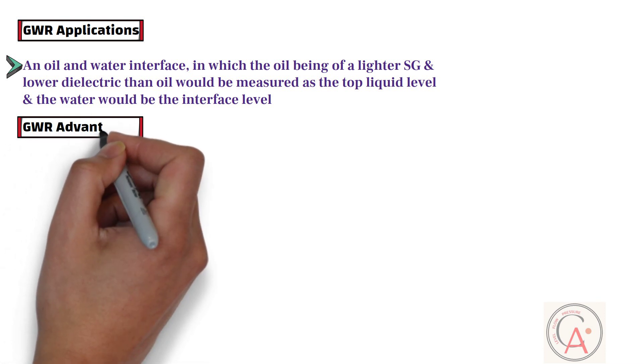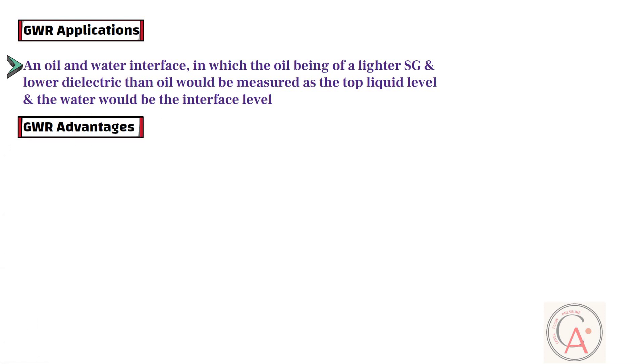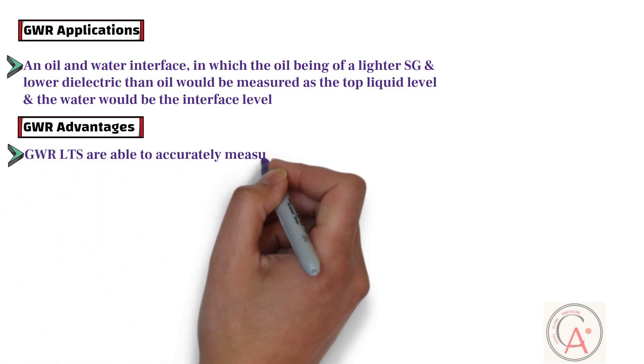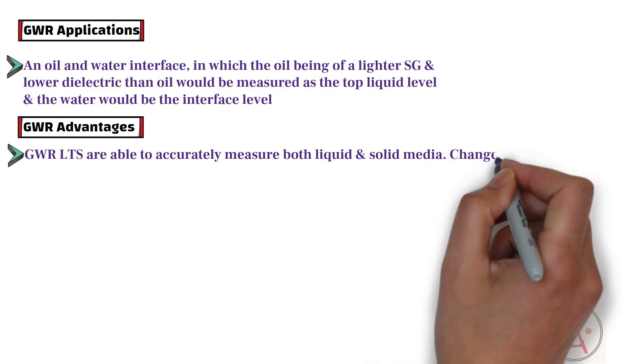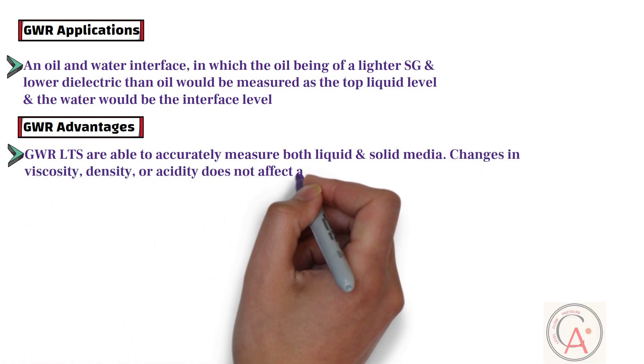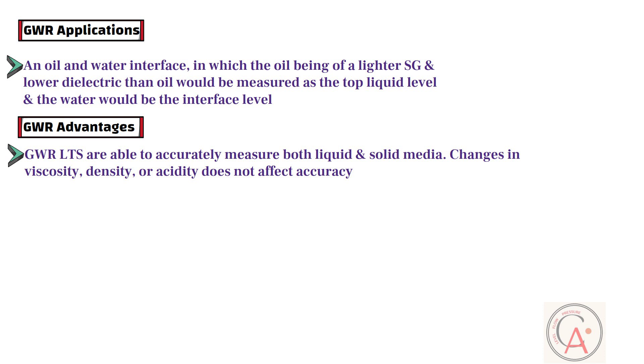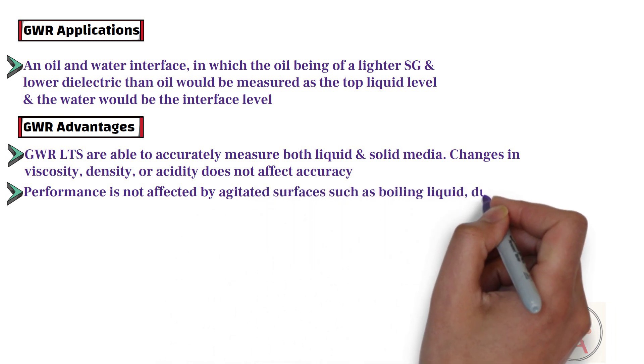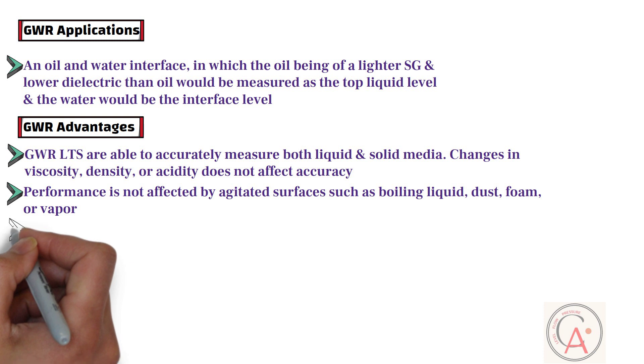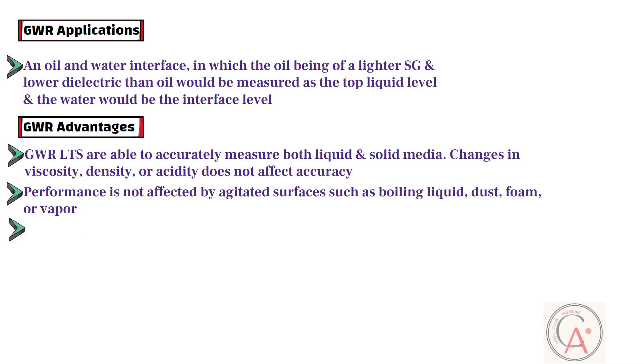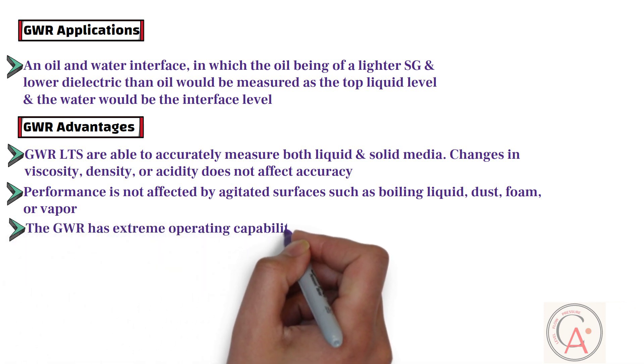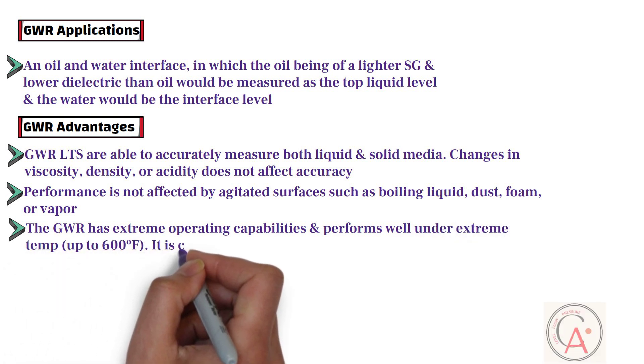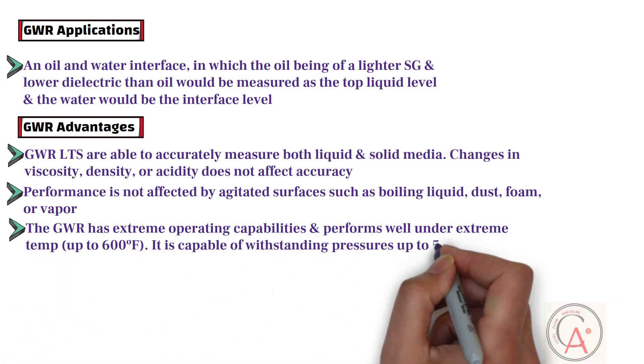Now let's learn some of the advantages of guided wave radar technology. Guided wave radar level transmitters are able to accurately measure both liquid and solid media, and changes in viscosity, density, or acidity do not affect its accuracy. In addition, this technology is not affected by agitated surfaces such as boiling liquid, dust, foam, or vapor. Furthermore, guided wave radar technology has extreme operating capabilities, performs well under extreme temperatures, and is capable of withstanding pressures up to 580 PSIG.